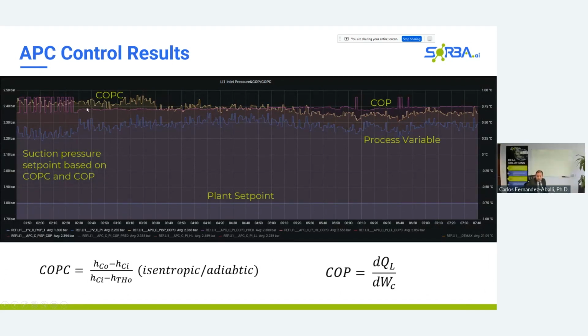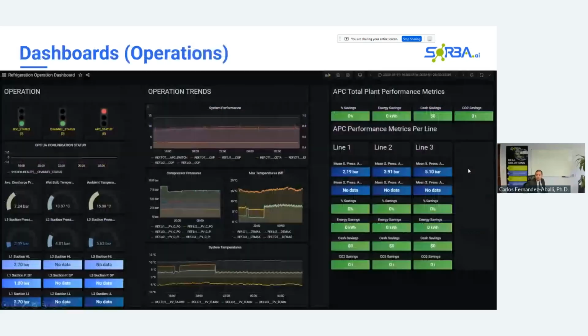Here we have a screenshot from a real result, and this plant has a fixed set point of 1.8 bars. Here we're controlling the suction pressure of the plant, and the blue line is where your process variable is, and the purple and yellow lines are where your cyclic COP and your isentropic COP process variables would be seen. As you can see, they're both concurrent, so they're both achieving the same kind of optimization. In both cases, during this time period of about 6 hours, we would be saving energy, relaxing the process variable from the blue line up to where the purple or yellow line is.